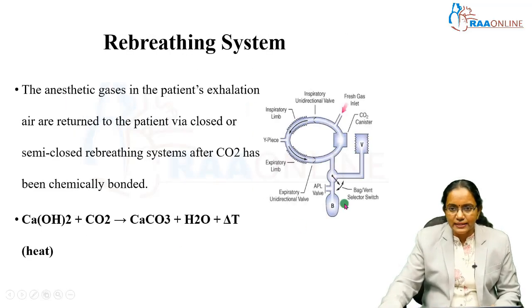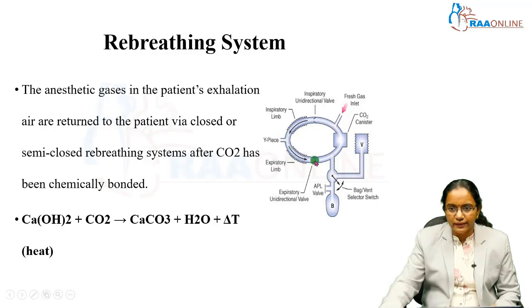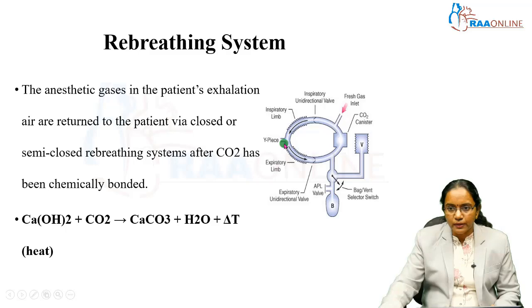This is a classic example of a re-breathing system where the anesthetic gases in the patient's exhalational air are returned back to the patient. This is the Y piece, this is the inspiratory limb, and this is the expiratory limb. There is a one-way inspiratory unidirectional valve and a one-way expiratory unidirectional valve. This is the fresh gas inlet where the fresh gas flow enters. It is taken via the inspiratory limb into the patient, and from the patient it comes back through the expiratory limb into the carbon dioxide canister.